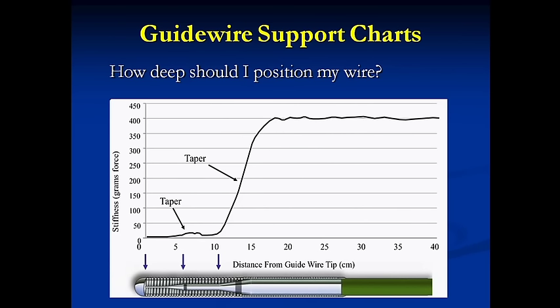Now the next thing to understand is this graph. The y-axis has the stiffness, and the x-axis has the distance from the guide wire tip. So this graph tells you what the stiffness is at different parts of the wire as you get away from the tip. For example, with different tapers, at about 18 or 20 centimeters from the tip, you kind of have a constant level of stiffness. The clinical relevance is, if you want to deliver devices, you ideally want it to be over the stiff part of the wire, so you want at least close to 20 centimeters distal from the lesion. This way you can know how deep to position your wire - you really don't have to go very deep. And this also tells you that if you can't go deep, and if the flimsy part of the wire is in the lesion, then you probably have to pick a different kind of wire.